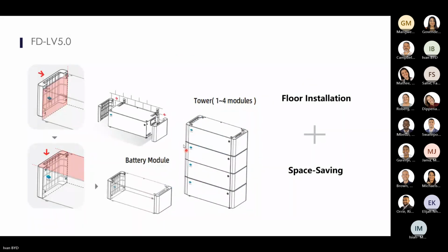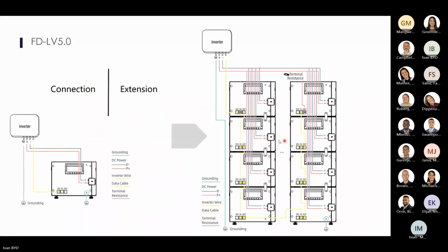Here's how it's installed. Mount it to the wall, and you can put up to 4 modules on top of each other. Here's the wiring. You won't be able to daisy chain these batteries because they can carry a huge amount of current. So, for example, your bottom battery does 70 amps, and if you daisy chain them, it goes 70, 140, 210, 280. So daisy chaining can really cause a lot of current to flow through a connector, and those connectors aren't designed for daisy chaining. So you have to take each cable to a common connector or a bus bar.